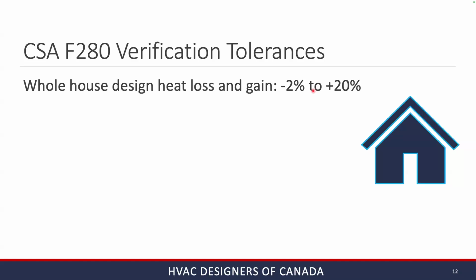The one that's in F280, for air conditioning and heat gain, is that you select equipment between 80% of the design load and 125%.